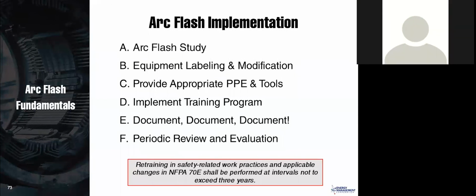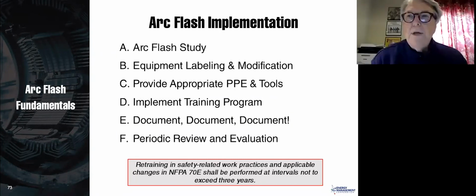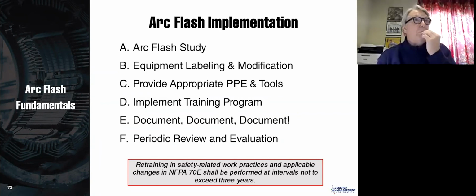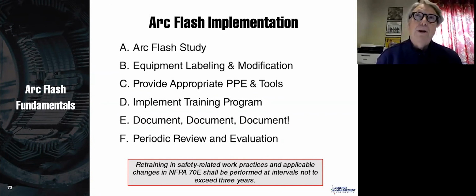All right. The next question we have is, our facility has the arc flash labels from 2014. Do we need to reassess the labels? Yeah, and the answer is no, you were good. But here's what I would do: walk into your facility and ask yourself, has anything changed? If you added a panel board someplace, all you need to do is add an arc flash sticker to that panel board. But if you put in a new transformer, let's say the utility put in a new transformer that's much bigger or even smaller, or you change the whole distribution system, yeah, then you are going to want to go ahead and reevaluate that. But for the most part, you don't.